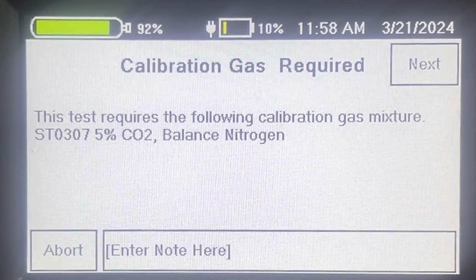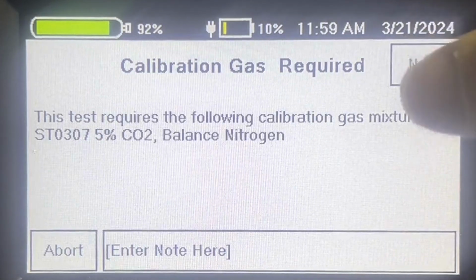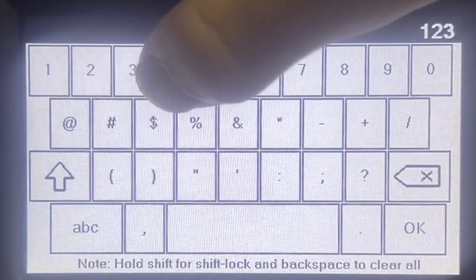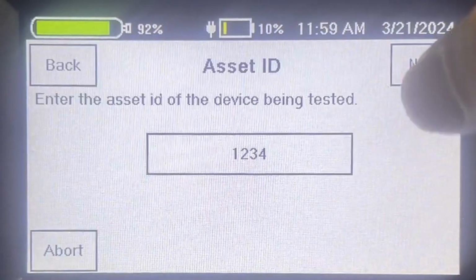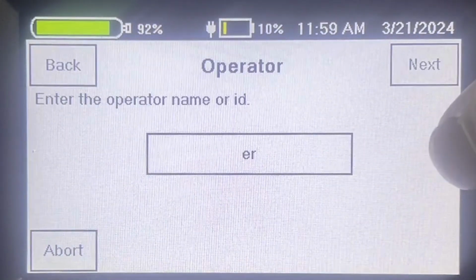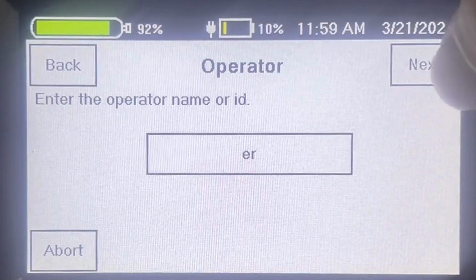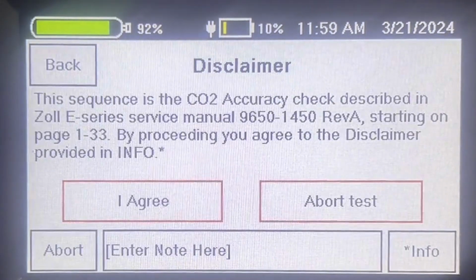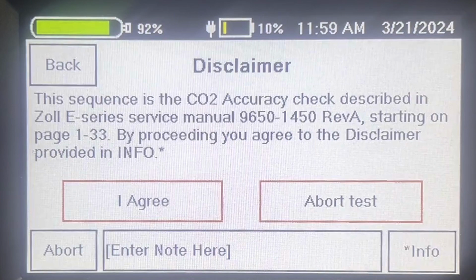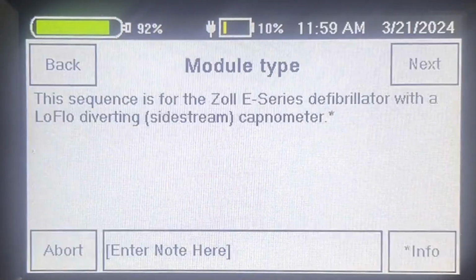First of all, it's going to want us to make sure that we have the correct cal gas, 5% CO2 balanced nitrogen, which I've put into the Smart Tank, so I'll click Next. Asset ID. Today, we're just going to use 1234. Operator name or ID, just my initials today. Disclaimer, making sure that the tester knows what they're getting into, knowing that this test sequence came from the service manual. So I agree to this. I am doing this test.